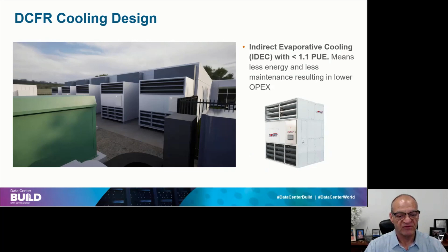I like the IDEC because it checks the boxes against chilled water, direct air, and pumped refrigerant. It has a low amount of points, it's simple from a complexity standpoint, and I'm only using partial mechanical cooling to achieve that. It has very low water usage, a very fast restart time, and the potential for contaminants is nonexistent, because I'm not introducing anything inside the environment, everything is external to the building.